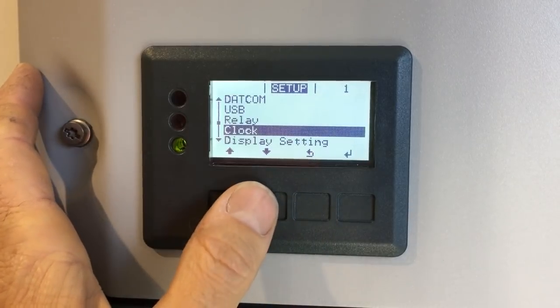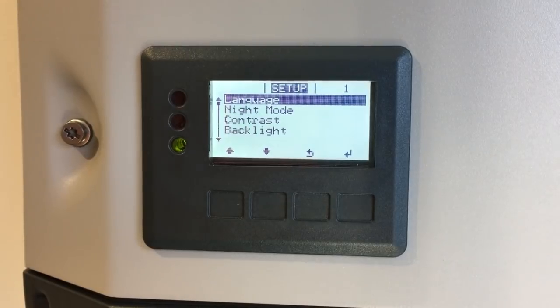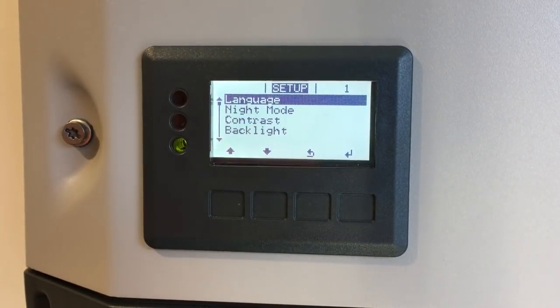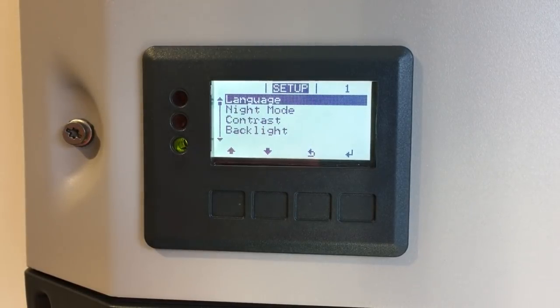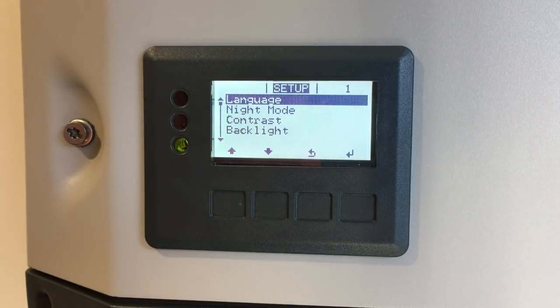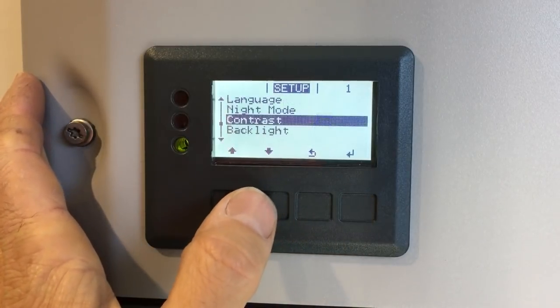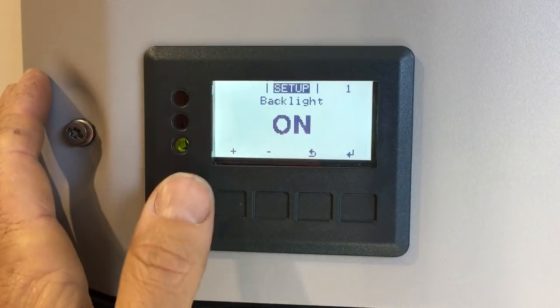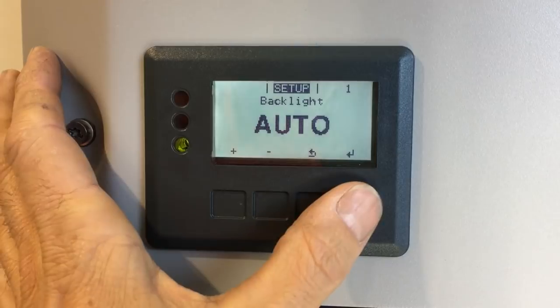There's a relay menu to test the relay on the data manager card, and a clock setting to set the time, date, and daylight saving mode. Display settings allow changing the system language. Night mode keeps the inverter operational and tracking grid voltage and frequency at night — this is very important if you're using a Fronius Smart Meter, because without night mode turned on the inverter shuts down after dark and won't log night-time consumption data. Contrast adjusts screen brightness, and backlight can be set to auto, always on, or off.